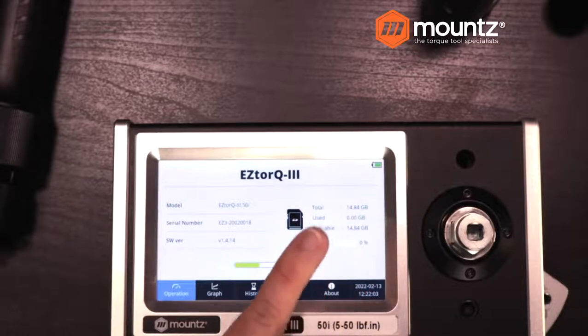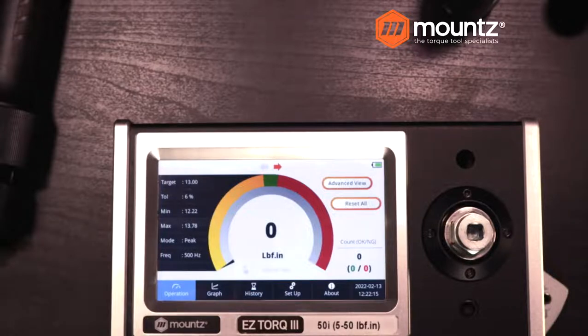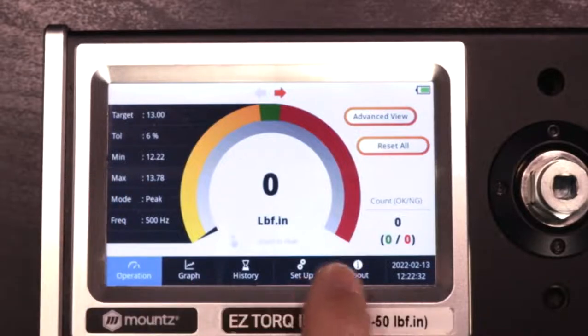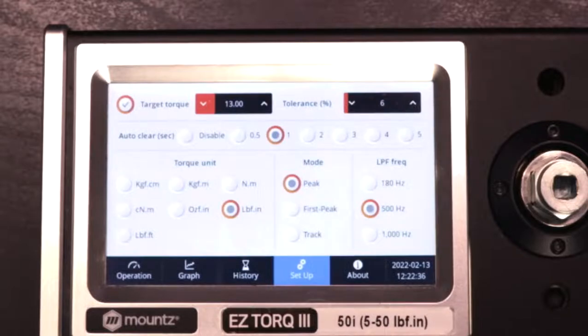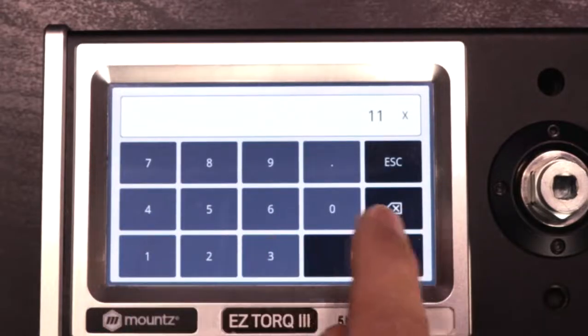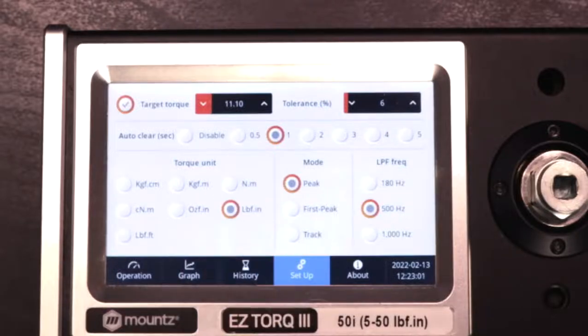In the setup menu, going to number one setting, we can enter in what our target torque is. If our torque is 11.1 inch pounds and we have a tolerance of 6%, we can also adjust how we would like the system to clear. I have it set to automatically clear after one second — it can be anywhere from 0.5 up to five seconds. When we are doing testing of a tool, especially if it's not in use, you want to warm the tool up and exercise it a little bit — about five times or so — before doing the actual testing.